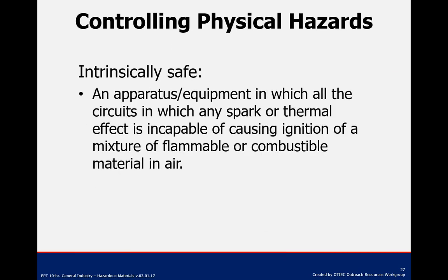Intrinsically safe apparatus: equipment in which all circuits are such that any spark or thermal effect is incapable of causing ignition of a mixture of flammable or combustible material in air under prescribed test conditions as described. So something deemed intrinsically safe typically has enough controls in place to prevent it from igniting.